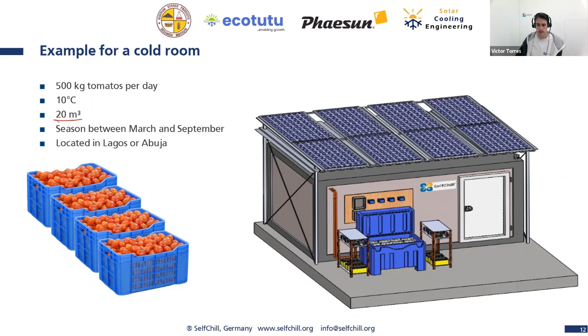Why not storing tomatoes? I have written down here the season between March and September. For a solar cooling system, we would like to utilize the cold room all over the year, but we are going to concentrate on this season. Tomatoes need a temperature of around 10 degrees, or no less than 10 degrees. So we will design the system for 10 degrees, and the cold room size will be 20 cubic meters. So this is the sample we are going to have today, and we will be having a look at the different equations based on what we have here.